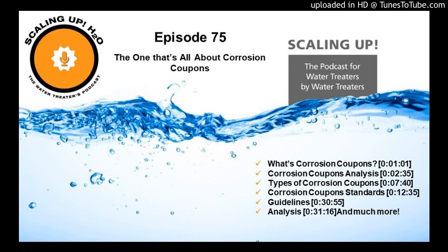Like I said, work with the manufacturer that you're getting a lot of your pumps and controllers from now. I am sure that they have corrosion coupon holders, but what they've done is manufacture these so you will get the same results as we were just referring to in the G4.